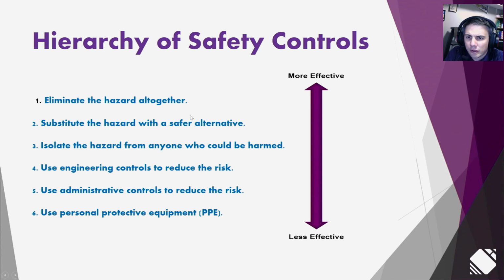Substitute the hazard with a safer alternative. Instead of repairing this equipment, can we use an existing and already set up transfer switch to bring power from a different source? Isolate the hazard away from anyone who could be harmed. That would be if you are switching high voltage equipment. Even just switching a breaker has a risk of arc flash. So what's available for sites now is actually robotics. They'll put a robot in the electrical room. They remotely just use a control and drive that robot up to the piece of switchgear.